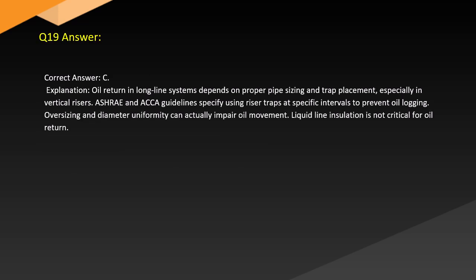Answer. Correct answer: C. Explanation. Oil return in long line systems depends on proper pipe sizing and trap placement, especially in vertical risers. ASHRAE and ACCA guidelines specify using riser traps at specific intervals to prevent oil logging. Oversizing and diameter uniformity can actually impair oil movement. Liquid line insulation is not critical for oil return.